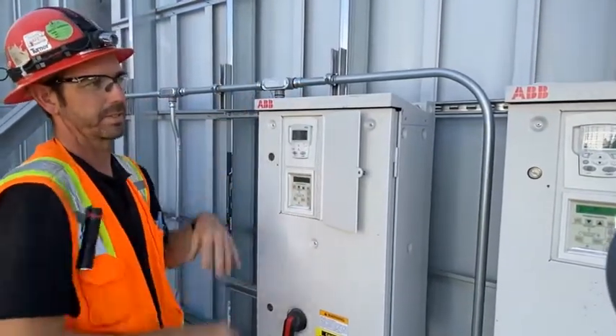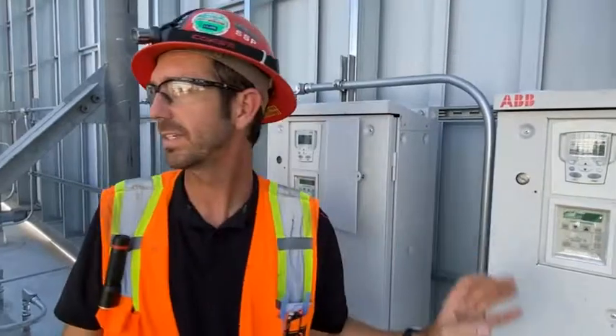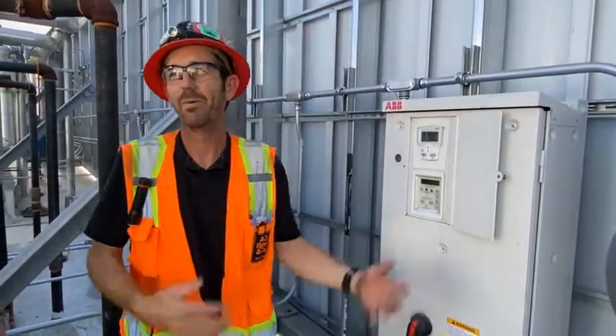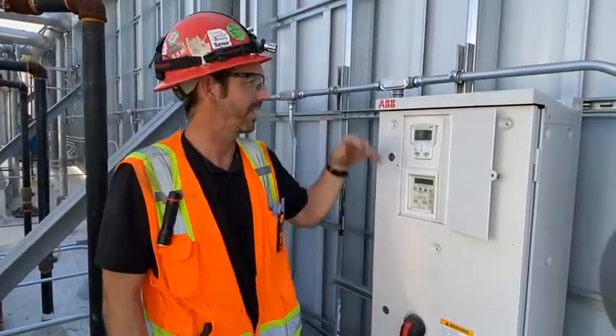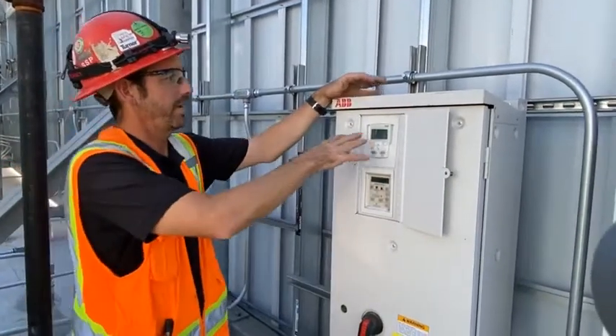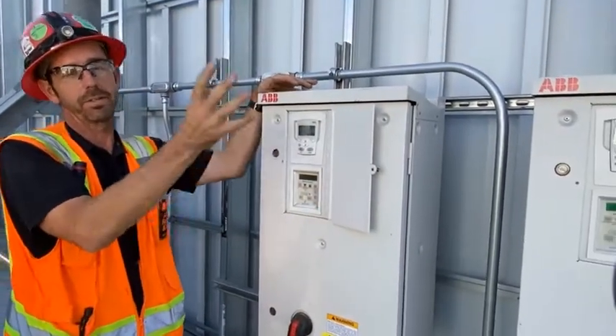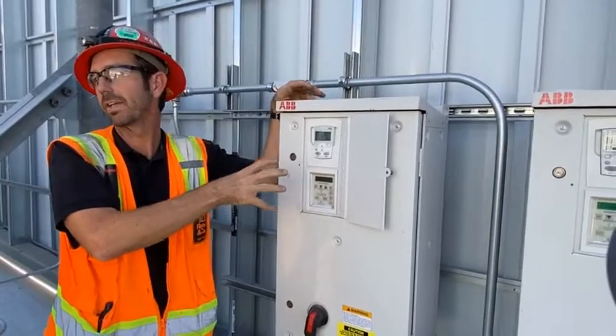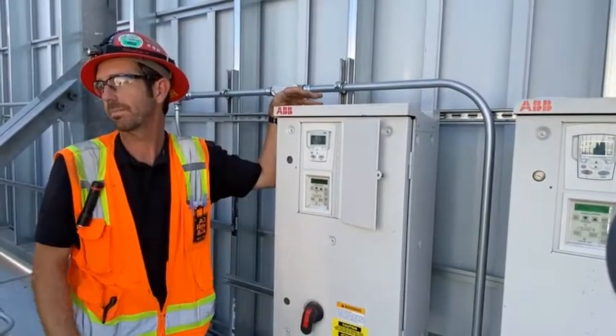And now all the zeros match. Could have been an OCD thing, I don't know. It wouldn't have made a difference, it just looked weird. It didn't match all the other ones. Okay? So that's how you would change out the drive: if you had to change out the drive, you could download those parameters back into the new drive. And you're like, okay, good, all the parameters now are the same as the old configuration.